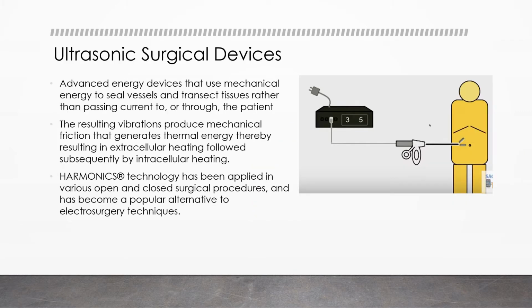The ultrasonic surgical device is an advanced energy device that uses mechanical energy to seal the vessel and transect the tissue rather than passing current to or through the patient. The resulting vibration produces mechanical friction that generates thermal energy, resulting in extracellular heating, followed subsequently by intracellular heating. Harmonic technology has been applied in various open and closed surgical procedures and has become a popular alternative to electrosurgery techniques.